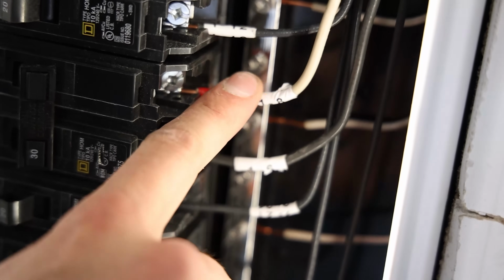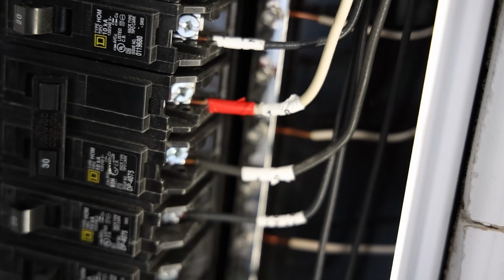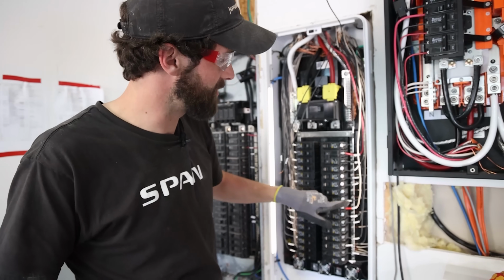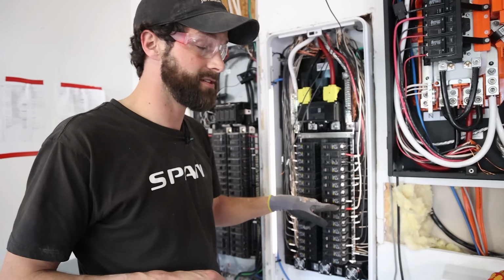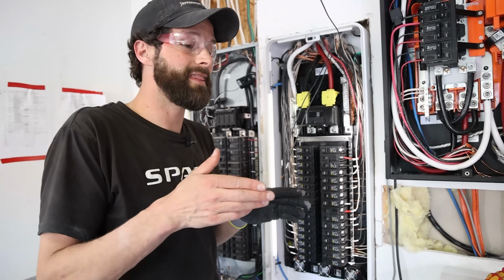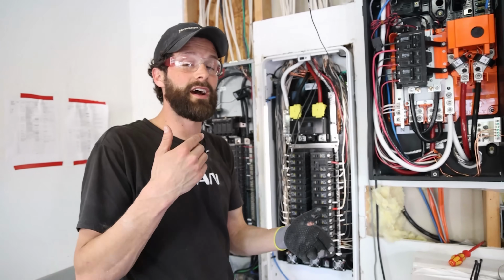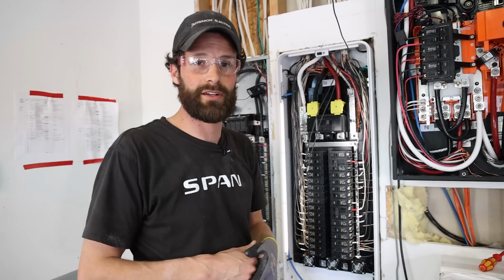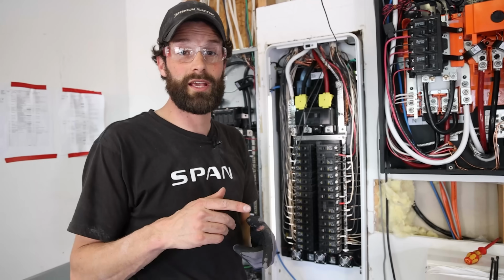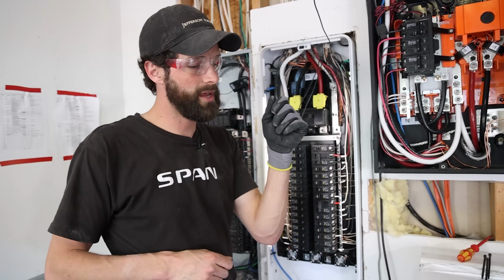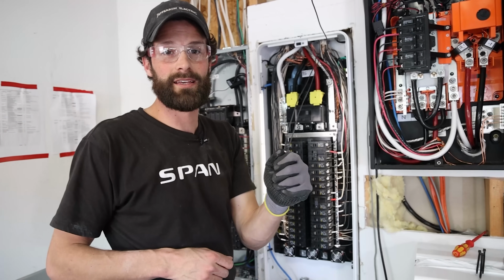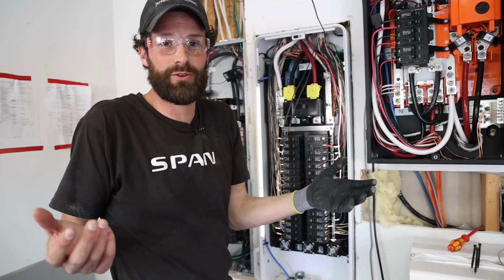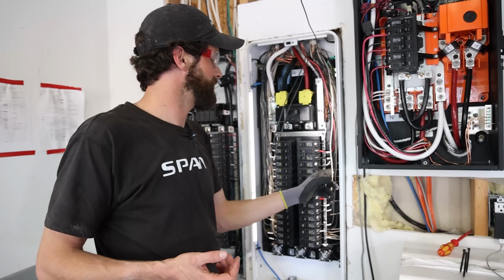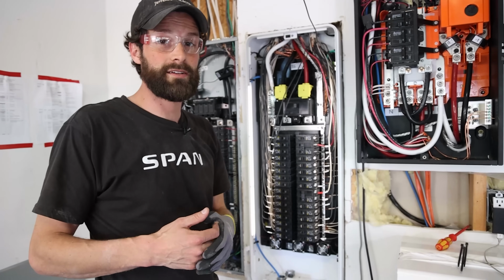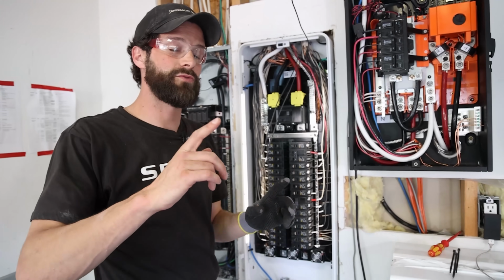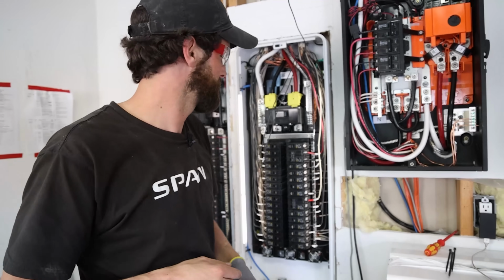Check out this white conductor here. Here's a code thing for you. This circuit on a 2-pole 30 is an air conditioner, so the white conductor is terminated to the breaker. In this case, the white conductor is an ungrounded conductor or hot conductor. So it's got to be relabeled at terminations. The code allows for that when a cable assembly, because you can't, right, electricians don't manufacture cables. When a cable assembly has a white conductor, it's permitted as long as it's re-identified at terminations.